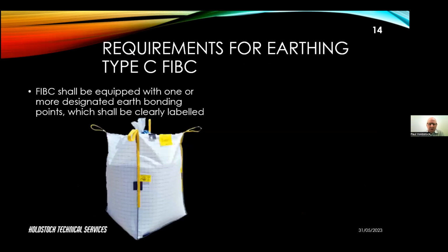So what are the requirements for earthing type C? Well, the FIBC, according to the standard, shall be equipped with one or more designated earth bonding points, which shall be clearly labelled. So this is a picture of a type C FIBC, and you can see the big safety label, which contains all that important information for the user, clearly displayed. So this is telling the user that the FIBC needs to be earthed. And then we have these designated earth bonding points, and these need to be accessible on all sides of the container. So whichever orientation the bag is, there's always an earth bonding point visible.